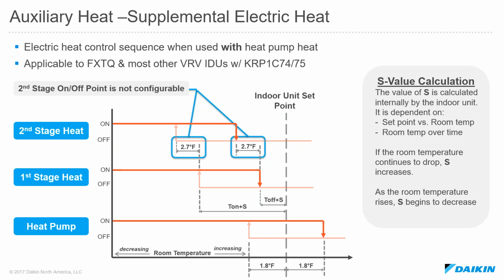meet set point. So there are configurable on values. Say you're 3 degrees away from set point, you can have it come on automatically. And then there are some electric heat options that are multiple stages. Some of the larger electric heat options go as high as 2 stages. So there's a second stage as well, which is not configurable. There is this S value. That's just an automatic setting that optimizes the on and off temperatures based off of trending of set point versus room temperature and your room temperature over time. It just optimizes those values automatically for you.